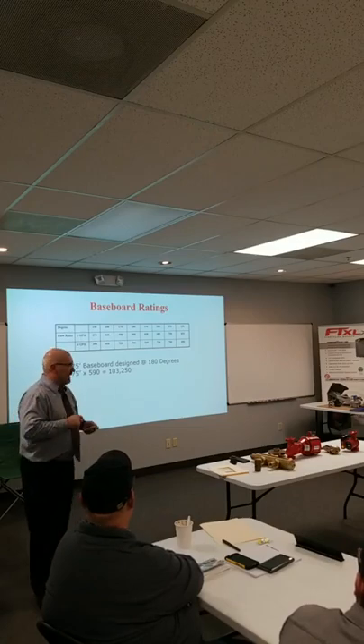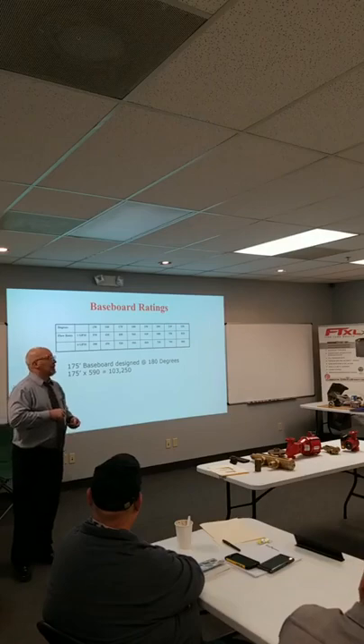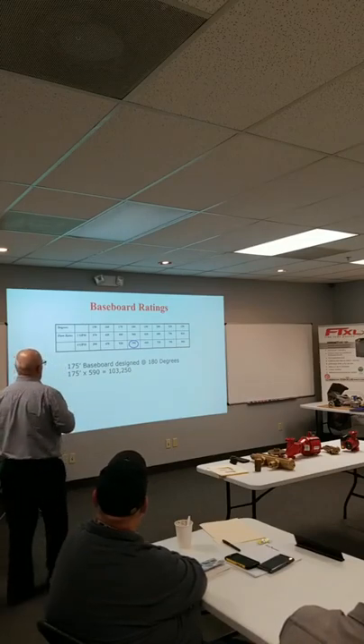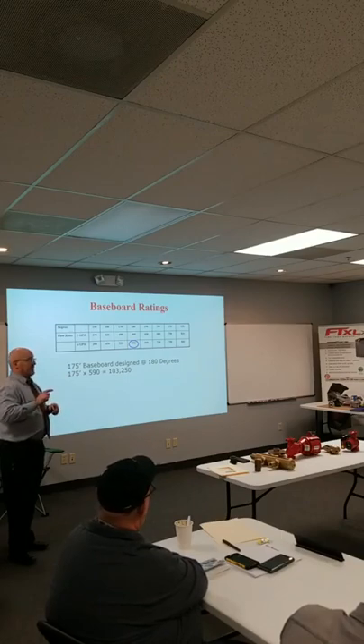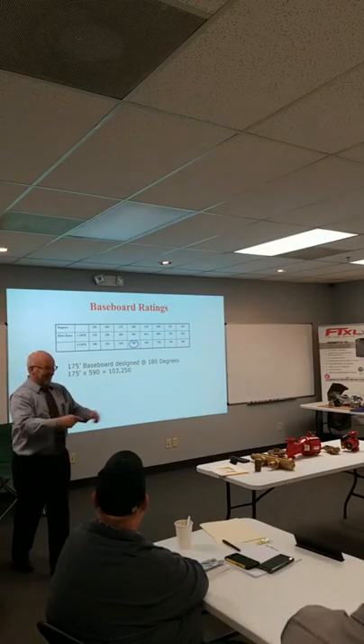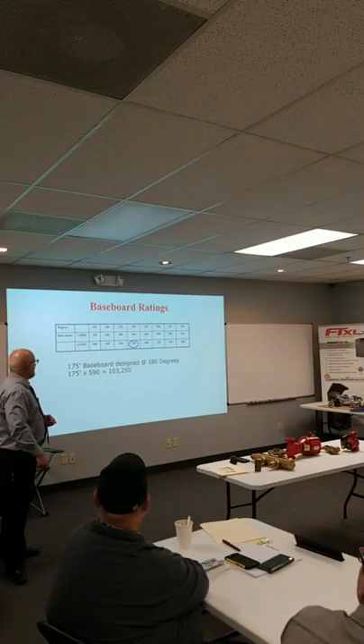But again, radiation doesn't determine what the heat loss is. That BTUs per hour or minute? Per hour. It's important. Very important. When we refer to BTUs, we always do it in hours, but it doesn't always get said. In our pump equation, we have to convert hours to minutes, because we're talking about GPM, which is in minutes, and BTUs in hours. That's where all that math comes in.